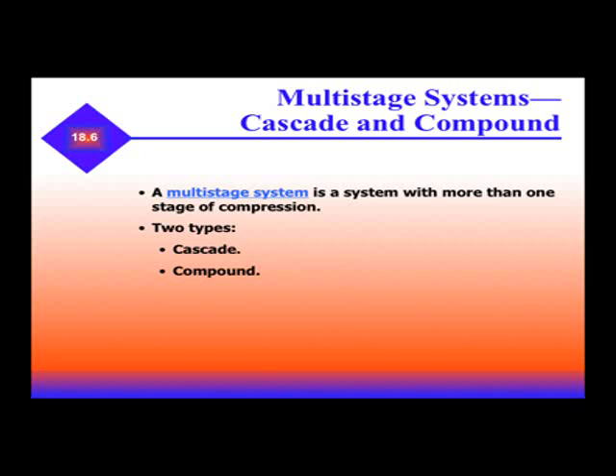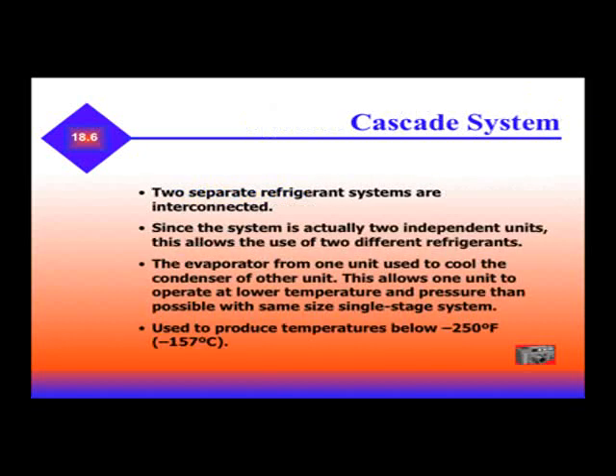Multi-stage systems can be known as cascade or compound systems. A multi-stage system is a system with more than one stage of compression. We have two types: cascade and compound. In the cascade system, two separate refrigeration systems are interconnected. Since the system is actually two independent units, this allows for the use of two different refrigerants. The evaporator from one unit is used to cool the condenser of the second unit. This allows one unit to operate at lower temperature and pressure than possible using the same size single stage system, and it's used to provide temperatures below negative 250 degrees.